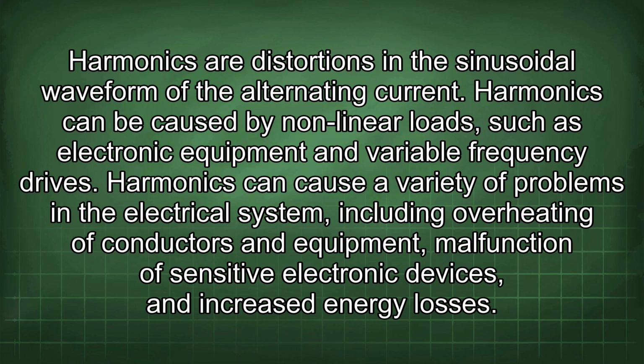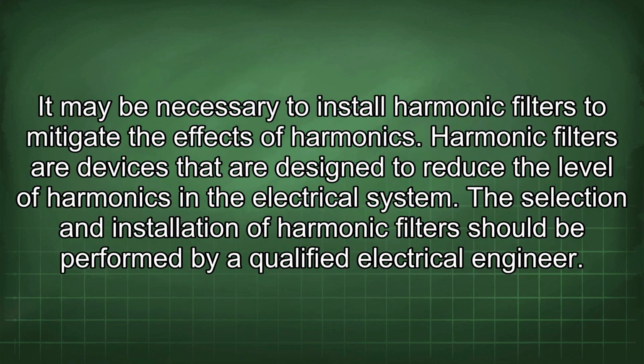Harmonics can cause a variety of problems in the electrical system, including overheating of conductors and equipment, malfunction of sensitive electronic devices, and increased energy losses. It may be necessary to install harmonic filters to mitigate the effects of harmonics. Harmonic filters are devices that are designed to reduce the level of harmonics in the electrical system. The selection and installation of harmonic filters should be performed by a qualified electrical engineer.